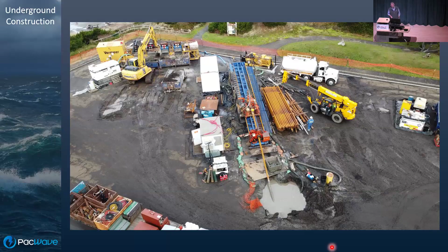Once we had all the conduit installed, the next piece at Driftwood was building a very large splice vault. We have offshore cables coming into the splice vault on the seaward side, and the splice vault is a transition from the very expensive offshore cables to slightly less expensive terrestrial cables. This vault is 74 feet by 16 feet, 10 feet tall.